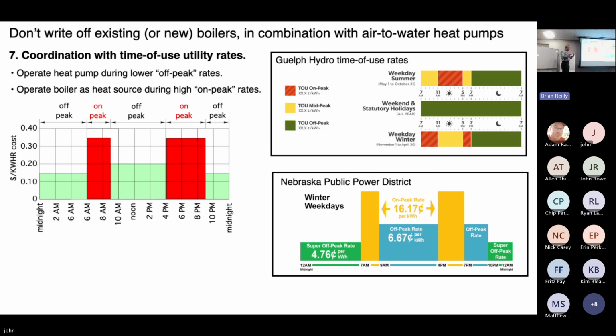And it might be a compromise. You might have to run 1 hour on on-peak rates. It all depends on storage, the load characteristics, the capacity of the heat pump, and so forth. But the ability to coordinate with on-peak and off-peak rates, especially now that you have water in the system. Remember, water is the best stuff on earth for sensible heat storage. Water is 3,500 times better than air at storing heat. So thermal storage tanks or buffer tanks, a slab with tubing in it, that's a tremendous amount of heat storage potential. So think about how all that could be coordinated with operation of an air to water heat pump.